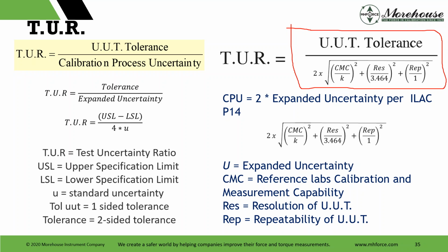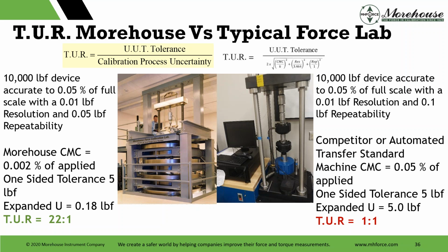And for further guidance, I suggest going to the ANSI Z540 handbook, which clearly defines the TUR denominator. When we look at this, primary lab versus a typical force lab, or Morehouse versus a typical lab, this could be primary lab versus secondary lab. I have 2 devices here, same exact device, same exact accuracy statement, same exact resolution. Repeatability, not exactly the same. It's not going to make that much difference.